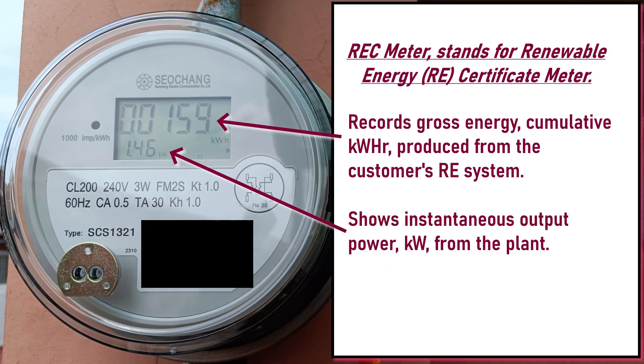This is the other meter installed in my net metering setup. This is called the REC meter, or the renewable energy certificate meter. The utility uses this meter to measure the gross electricity generated by the renewable energy system, in this case my rooftop solar power plant. The readings from the REC meter will be used as a basis for the computation of subsidies, discounts, and for compliance with renewable portfolio standards. The gross electricity during a billing period is present reading minus previous reading.